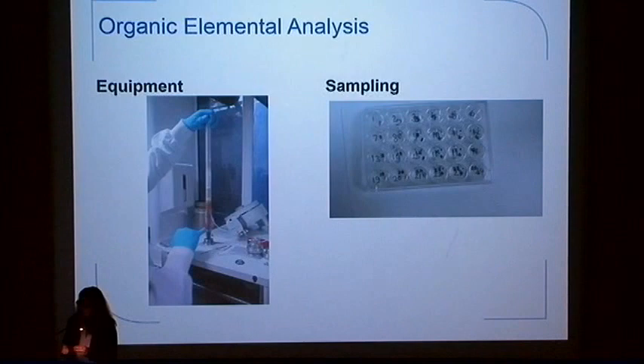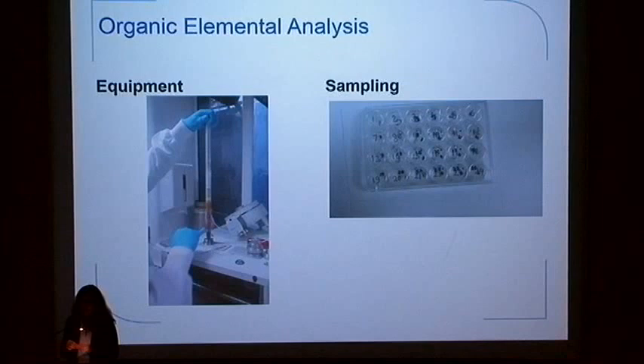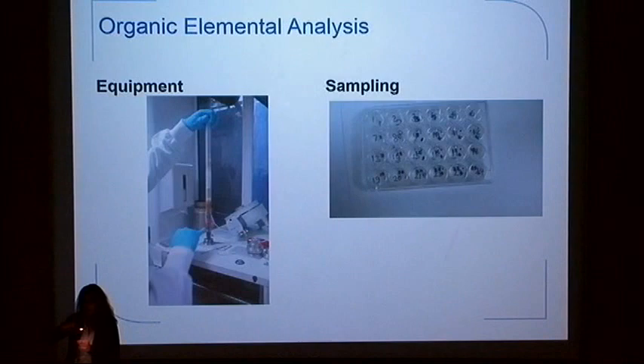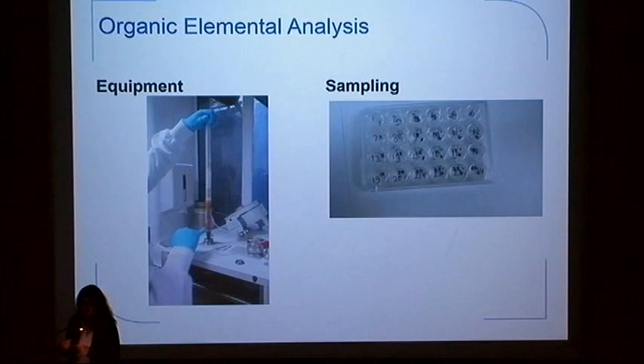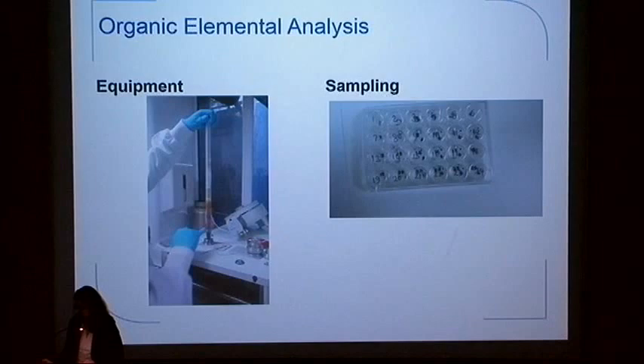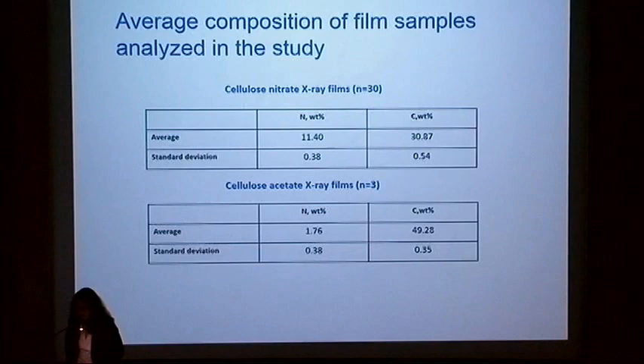Before analysis, the sample is placed into a tin boat and folded very tightly to exclude any trapped air. The sample required is minimal — as little as 0.2 milligrams — compared to what is needed for the float test. Once wrapped in the tin boat and placed in the autosampler, it is purged with helium to exclude atmospheric gases that could interfere with the readings. It is then burned in the furnace and the filters analyze the concentration of the elements.